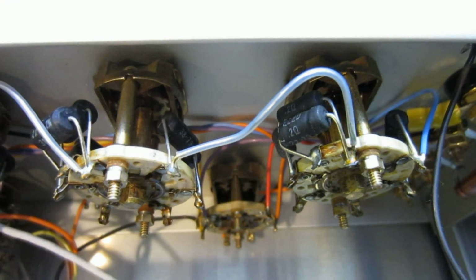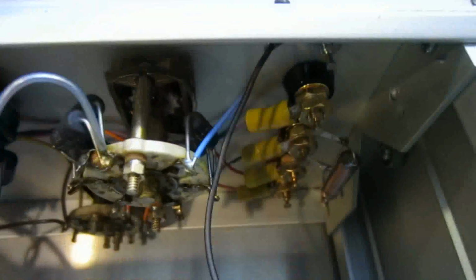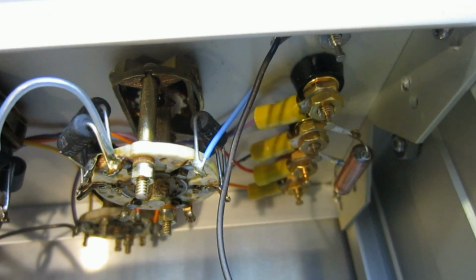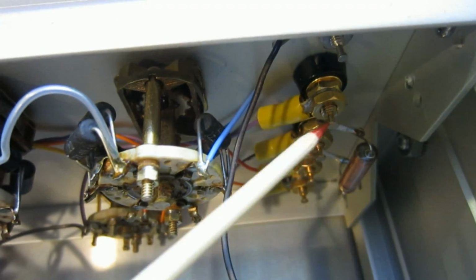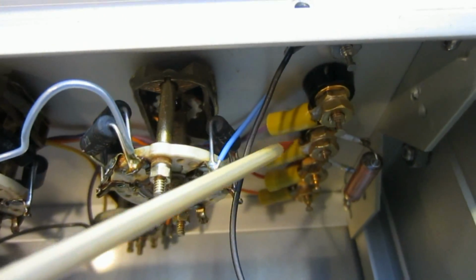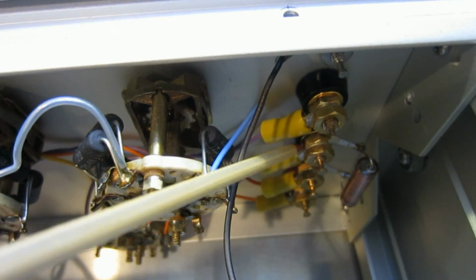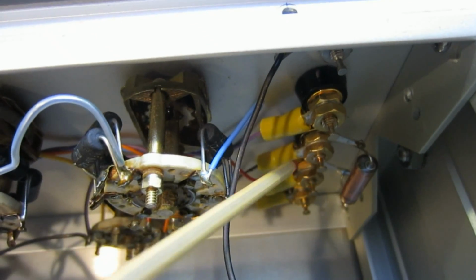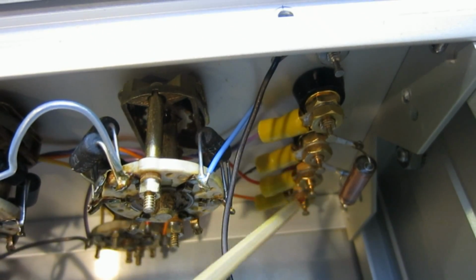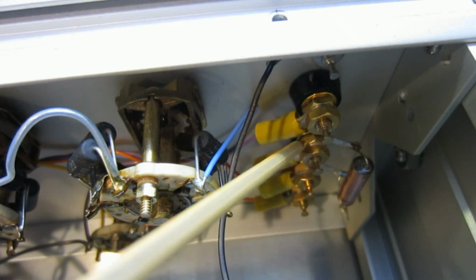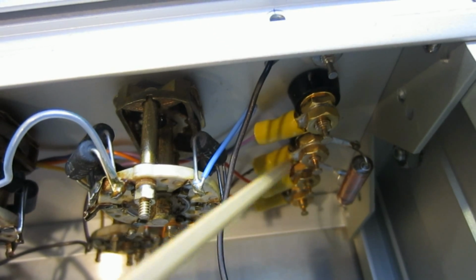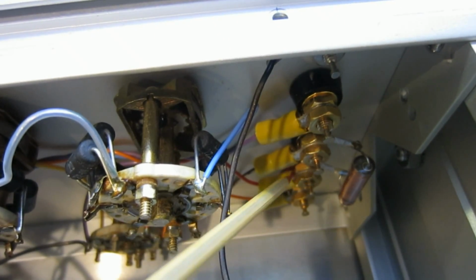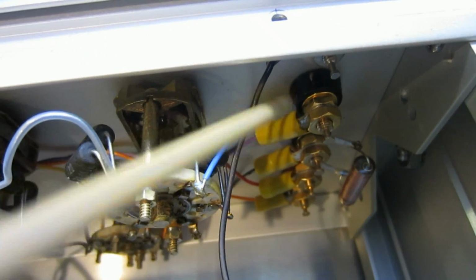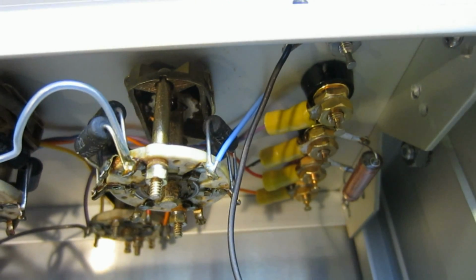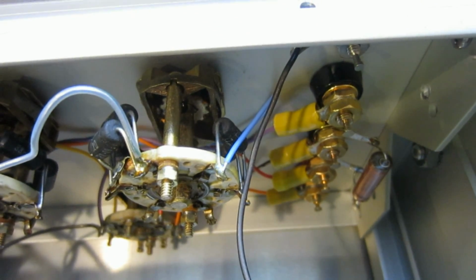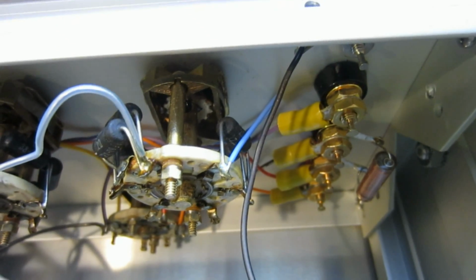Now there's some guidance on how to - here you can see the terminals leading to the outside. These are probably gold-plated terminals to make sure the contact resistance stays in check. You need to be careful when measuring, as these are 4 terminals - the sensing terminal and the output terminal need to be connected securely. If you just use 2 wires, the reading will jump all over the place, which is something a lot of people tend to forget.